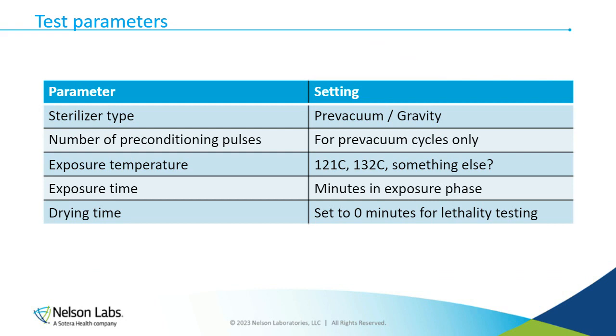When specifying the cycle in our test procedures and validation protocol, we need to specify whether we're validating a pre-vacuum or gravity cycle. If it's a pre-vacuum cycle, do we need to specify the number of pre-conditioning pulses? What is the exposure temperature, exposure time, and drying time? For lethality testing, we set drying time at zero minutes to represent worst-case conditions.